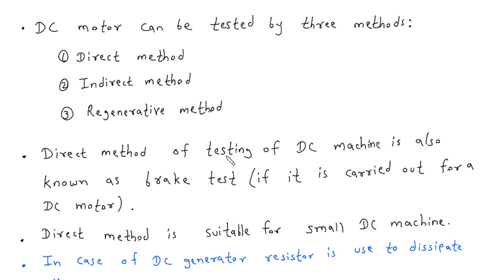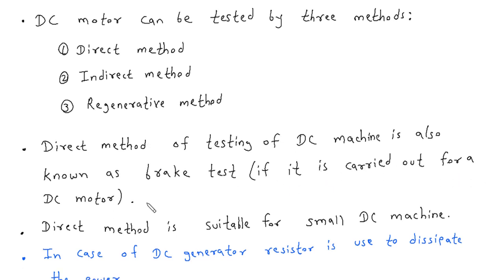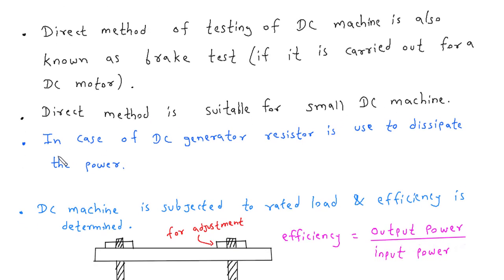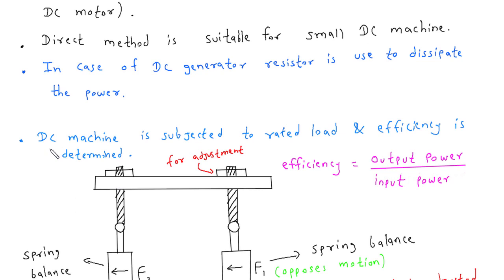Direct method of testing of DC machine is also known as brake test if it is carried out for a DC motor. Direct method is suitable for small DC machine. In case of DC generator, resistor is used to dissipate the power. DC machine is subjected to rated load and efficiency is determined. And we know the formula for efficiency is output power upon input power.